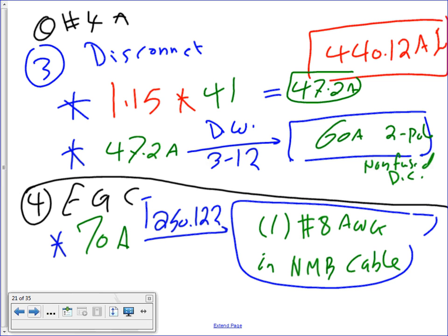And all of you guys, if you're in the field, if you think when you go sit in an engineering firm you're going to do all this calculation, think again. These will be done by a bunch of engineers before you. They have tables. They say, if you have this size of chiller, here's the size of the feeder and the conduits and the overcurrent protection device that I use with it, to standardize the process, including voltage drop, including continuous load, including bundling, whatever.